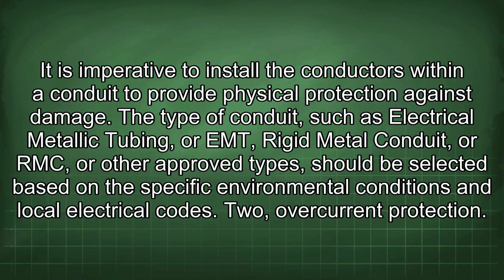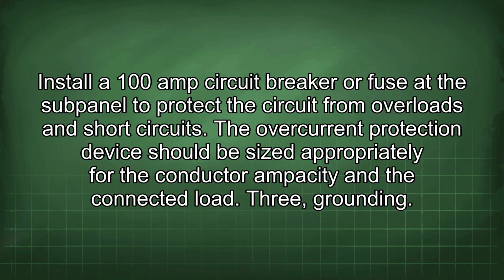2. Overcurrent protection. Install a 100 amp circuit breaker or fuse at the subpanel to protect the circuit from overloads and short circuits. The overcurrent protection device should be sized appropriately for the conductor ampacity and the connected load.